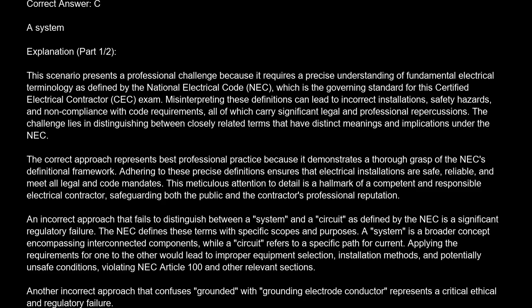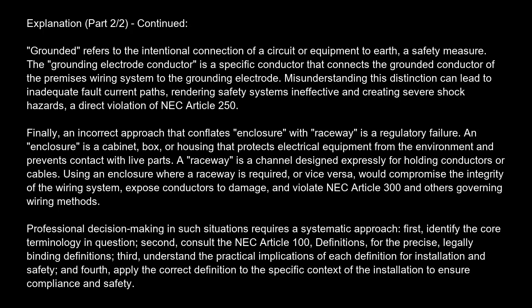Another incorrect approach that confuses grounded with grounding electrode conductor represents a critical ethical and regulatory failure. Grounded refers to the intentional connection of a circuit or equipment to earth, a safety measure. The grounding electrode conductor is a specific conductor that connects the grounded conductor of the premises wiring system to the grounding electrode. Misunderstanding this distinction can lead to inadequate fault current paths, rendering safety systems ineffective and creating severe shock hazards, a direct violation of NEC Article 250.